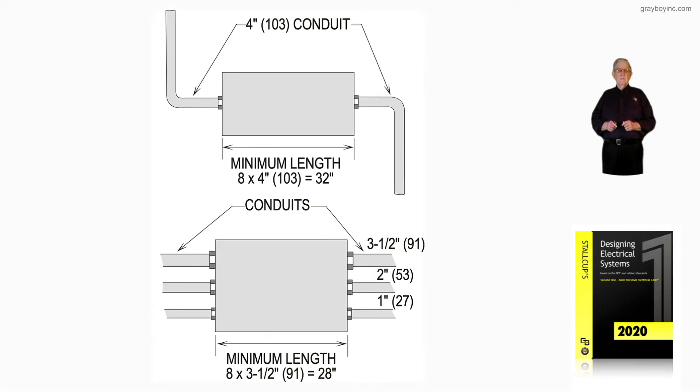This illustration now deals with a straight pull. I would like to point out that the conductor sizes now are number four or larger, not number six or smaller, or we'd be using the table 314.16A or B.